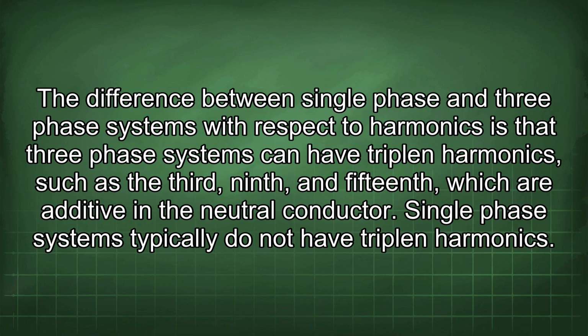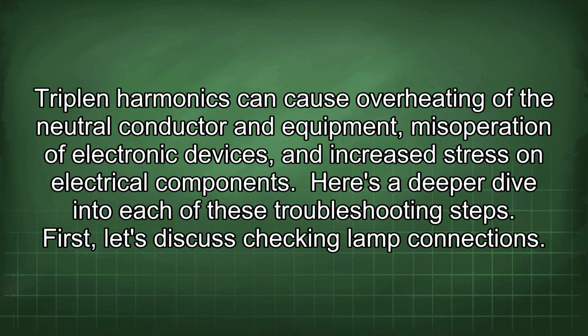The difference between single-phase and three-phase systems with respect to harmonics is that three-phase systems can have triplen harmonics, such as the 3rd, 9th, and 15th, which are additive in the neutral conductor. Single-phase systems typically do not have triplen harmonics. Tripling harmonics can cause overheating of the neutral conductor and equipment, misoperation of electronic devices, and increased stress on electrical components. Here's a deeper dive into each of these troubleshooting steps.